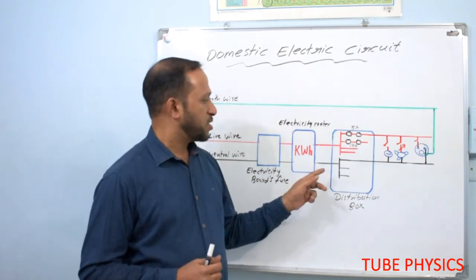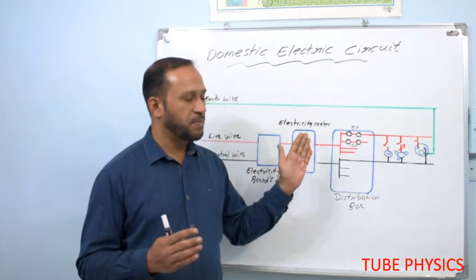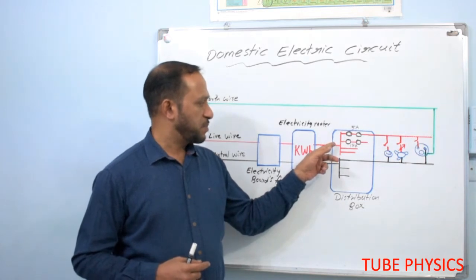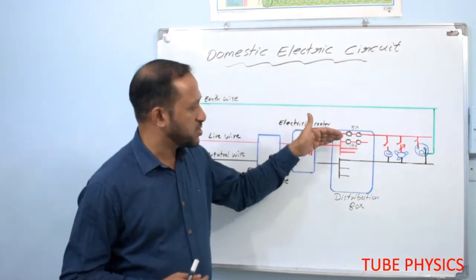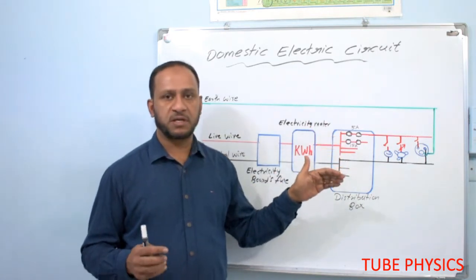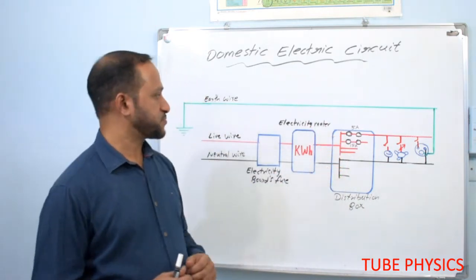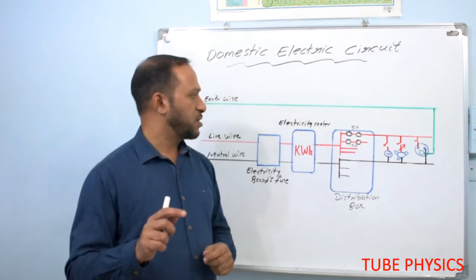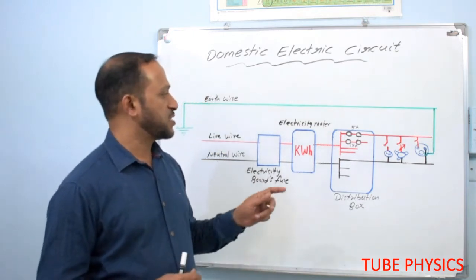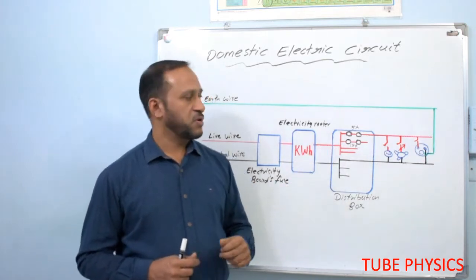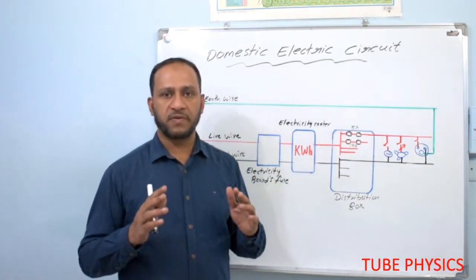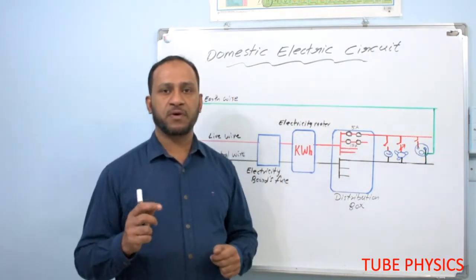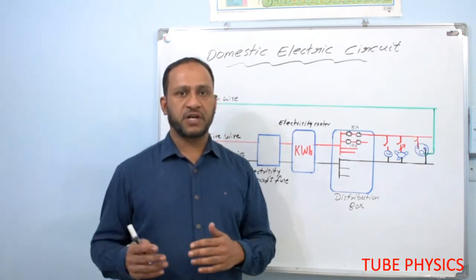The main distribution box is where we plan the number of branches needed for our circuit. In the main distribution box, we can connect a main switch and branch out the circuit into the required number of branches depending upon the need of the building. In each branch, we can have two standard lines: one for a current rating of 5 ampere, used for normal devices like bulbs and fans, and another for 15 ampere, used for high power devices like AC, geyser, and refrigerator.